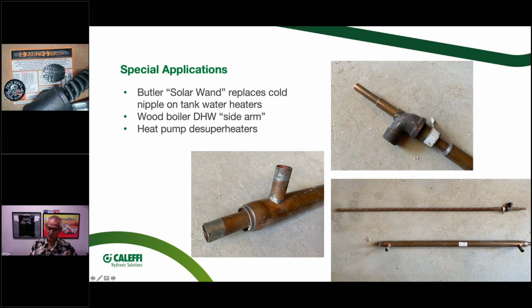A word of caution, you could certainly overheat a tank. You could get your domestic water heater up to 180 degrees. You can get it hotter than that, and we've had ones where they would pop the relief valve on temperature because they got them so hot, so you would want to put a mixing valve for sure on that type of application, because whatever temperature that wood boiler's running, you could essentially get that tank up to pretty close to that temperature. So if you see one of these on a job, I would highly recommend that you put a thermostatic mixing valve on whatever this is connected to, typically just a regular water heater tank. They typically call that a sidearm, domestic hot water sidearm.